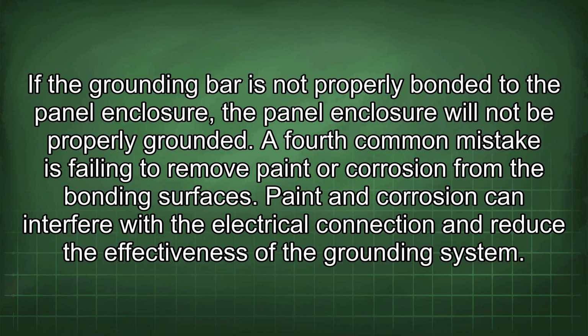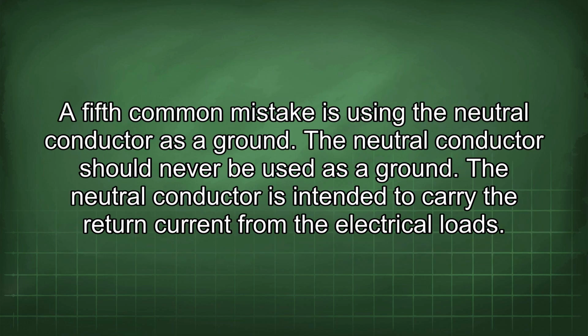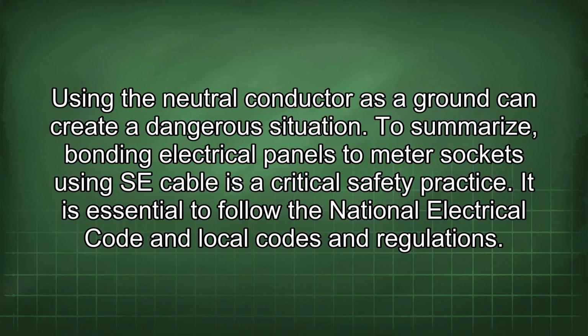If the grounding bar is not properly bonded to the panel enclosure, it will not be properly grounded. A fourth common mistake is failing to remove paint or corrosion from the bonding surfaces. Paint and corrosion can interfere with the electrical connection and reduce the effectiveness of the grounding system. A fifth common mistake is using the neutral conductor as a ground. The neutral conductor should never be used as a ground. The neutral conductor is intended to carry the return current from the electrical loads. Using the neutral conductor as a ground can create a dangerous situation.